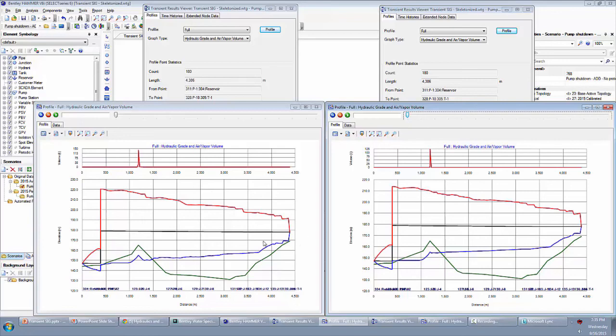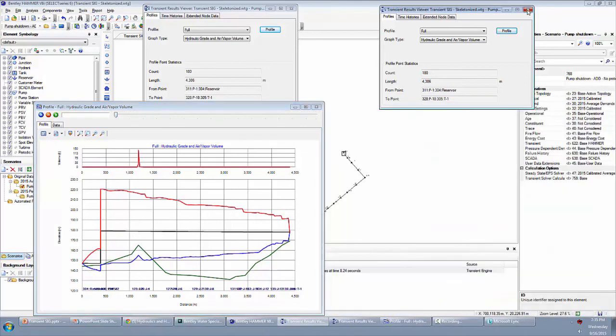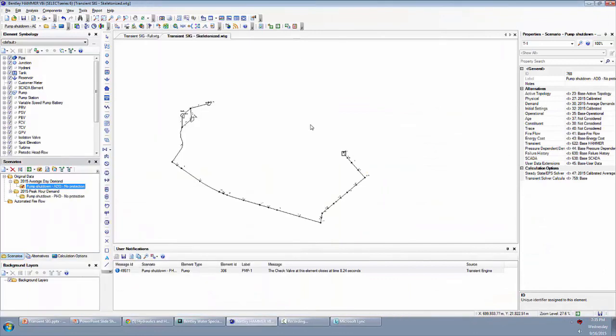Looking at the blue line, the minimum, looks like over here on the left side the pressures were a little bit lower up on this hill than they were over here. So one might conclude that maybe it doesn't matter too much, but in this case, we're going to go ahead and proceed off of the average day demand scenario to select that as our worst case scenario.